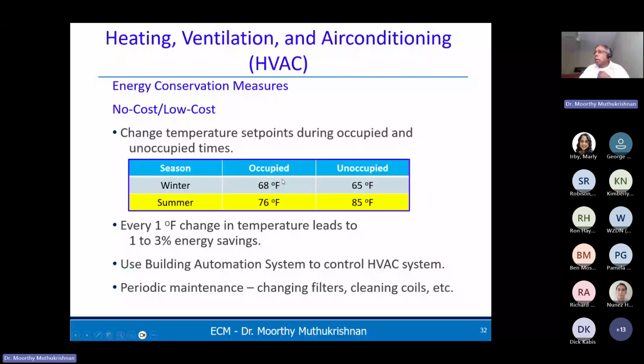That way, for every 1 degree Fahrenheit change in the temperature, it leads to about 1 to 3% energy savings, which is a pretty good savings. Now, all you have to do is just reduce the temperature. And during the summer, instead of cooling down to, let's say, 70 degrees or maybe 68 degrees, I've seen some places cool down to about 65. If it is not required, increase the temperature to maybe 72, 73, 74, and so on. Again, it's up to your comfort level, but it's a good idea to increase the temperature. And if it's not occupied, for example during the night hours and when there is nobody around during the weekends, increase the temperature even higher.